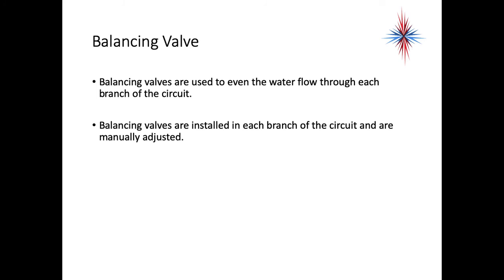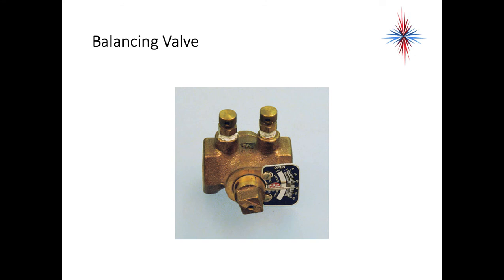Balancing valves even out water flow through each branch of a circuit and are installed at each branch for manual adjustment. You normally see them in commercial applications, large apartment buildings, or hotels. By attaching a balancing gauge and knowing the pipe diameter and inlet/outlet pressure, you can determine exact flow in gallons per minute. Once set, mark the position so it can be replicated if the valve needs to be replaced.